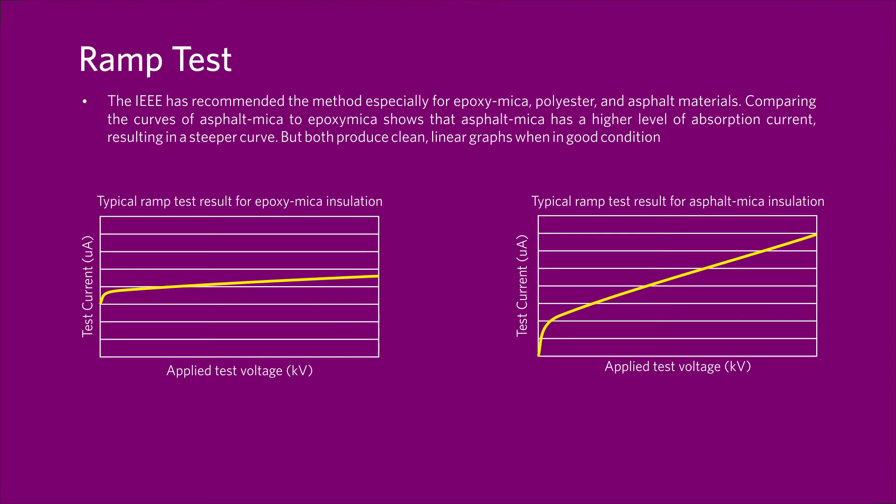The IEEE has recommended the method especially for epoxy mica, polyester, and asphalt materials. Comparing the curves of asphalt mica to epoxy mica shows that asphalt mica has a higher level of absorption current, resulting in a steeper curve. But both produce clean, linear graphs when in good condition.